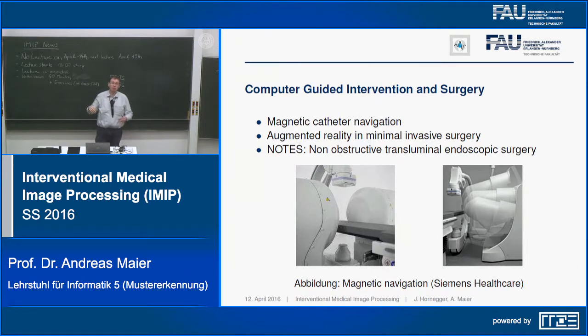Think of a typical intervention room, there's a lot of stuff around, many devices. First, you have to do a test run to see if you can do the motion without collision. Second, you can't move too quickly, because if somebody is in the way and you rotate the entire 200 degrees in 1 second, you may end up kicking one of the surgeons against the wall, which is not advisable. So typically the scans take between 20 and 5 seconds for the rotation.